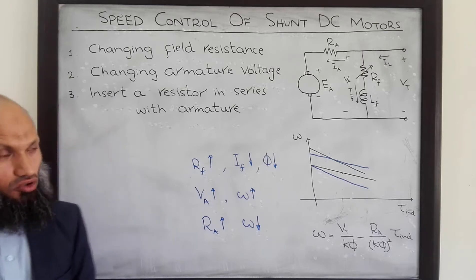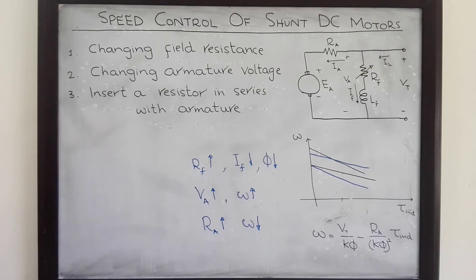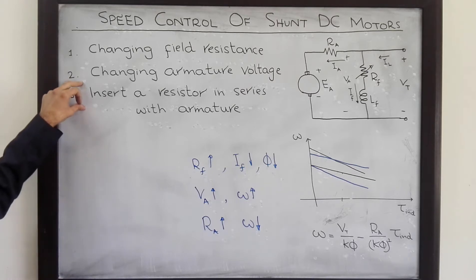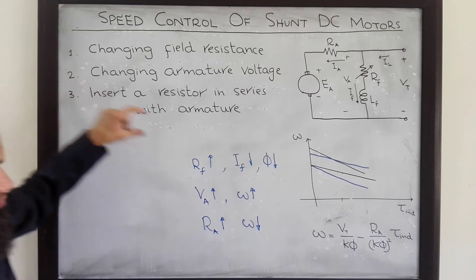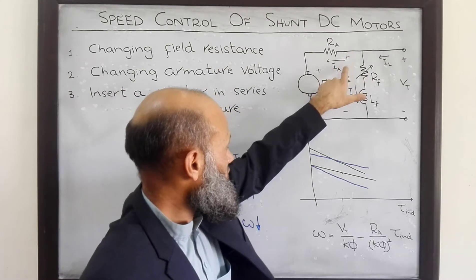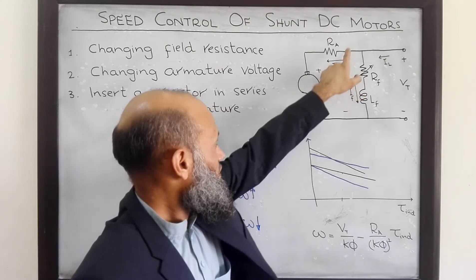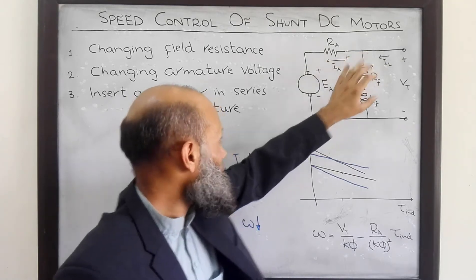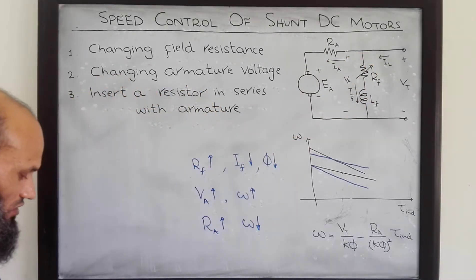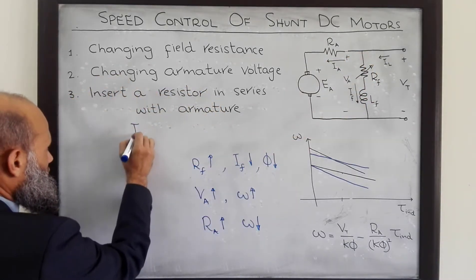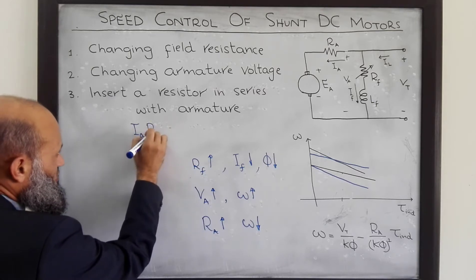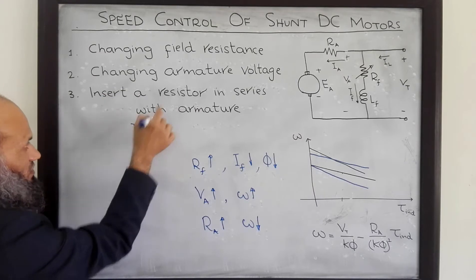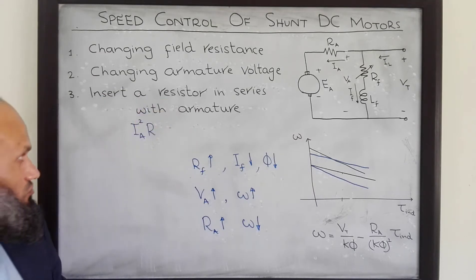Let's talk about the pros and cons of all these approaches. The armature resistance approach is not used very frequently because there is high armature current, and inserting a resistor there is associated with power losses in the additionally inserted resistor. That is why this approach is not very frequently used.